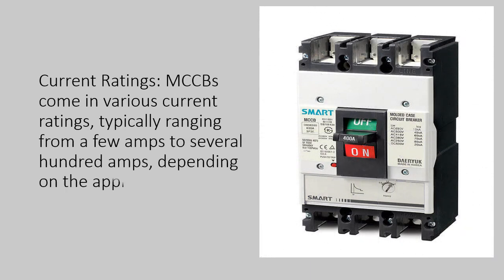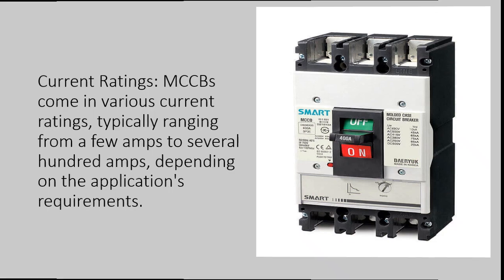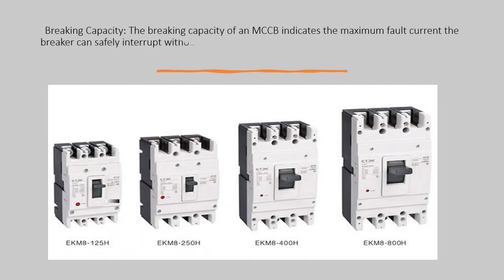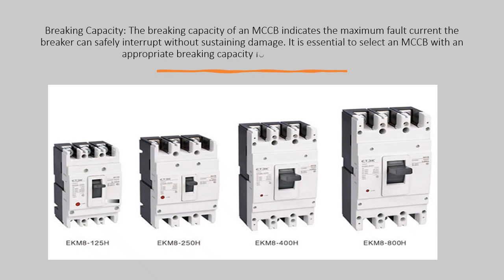4. Current Ratings — MCCBs come in various current ratings, typically ranging from a few amps to several hundred amps, depending on the application's requirements. 5. Breaking Capacity — the breaking capacity of an MCCB indicates the maximum fault current the breaker can safely interrupt without sustaining damage. It is essential to select an MCCB with an appropriate breaking capacity for the system it will protect.